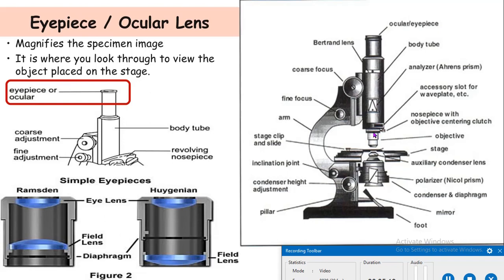The ocular or eyepiece magnifies the specimen image. It is where you look through to view the object placed on the stage. The removable lens assembly that fits into the top of the microscopic tube is called the ocular. The assembly consists of two plano-convex lenses: the small upper lens is called the eye lens and the large lower lens is called the field lens.